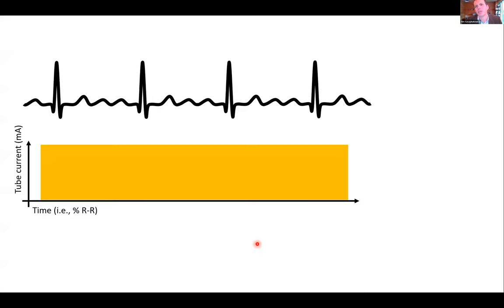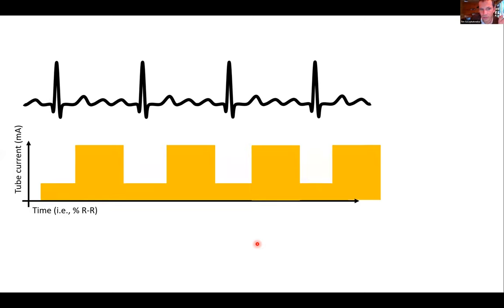To understand more about the range of ways a modern cardiac CT scanner can adapt, I'll flash through a few slides of what today's premium CT scanners can do. We won't get into all the vendor nuances since there are more than I'll ever understand, but for example, your scanner could opt into a pure retrospective mode with no mA modulation, where it just has a certain mA level, scanning data in a slow helical or spiral acquisition.